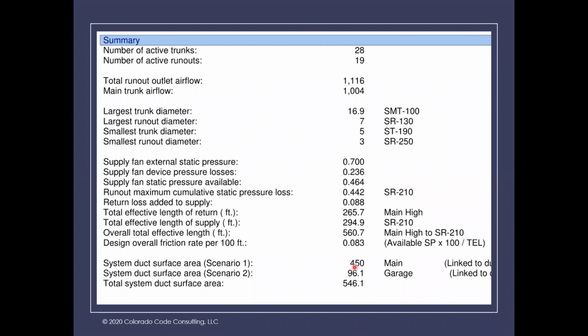Yeah, you can see what this one is, right? Total effective length, look at that bad boy. 560 feet, pretty typical, 500, 600, 700 feet for single families. Well, it's a production house, 2-story. So that's not unusual, but they're still good, right? Still good. 0.083.